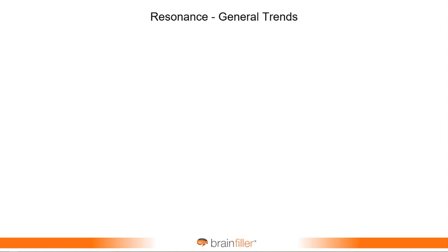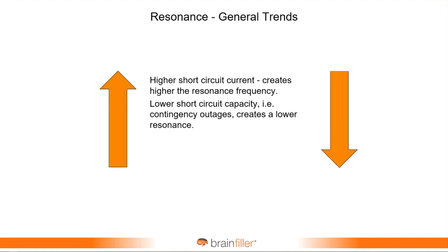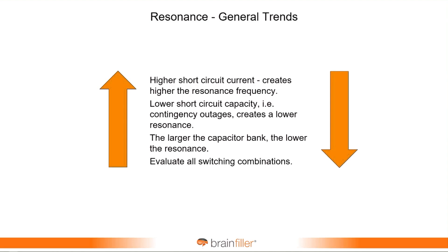The general trends are: the higher the short circuit current, the higher the resonance frequency, which normally is where you want to go — unless you're sliding up into like the seventh harmonic, which could be a problem. The lower the short circuit current, the resonance frequency tends to become lower. And in general, when you have resonance and harmonics at lower frequencies, that tends to cause bigger problems because you have larger harmonic currents at lower frequencies. Also, the larger the capacitor bank, the lower the resonance; the smaller the capacitor bank, the higher the resonance. The more capacitors you put online, the larger the bank, the resonance frequency shifts lower.